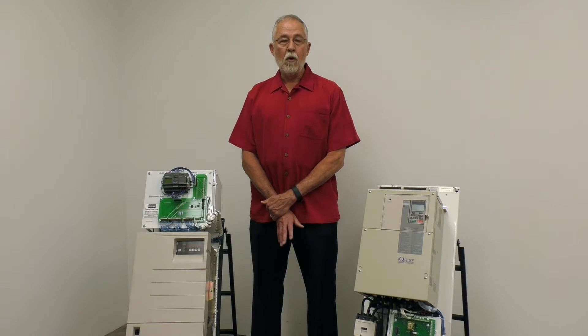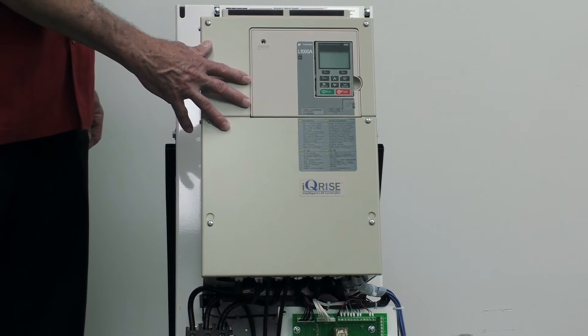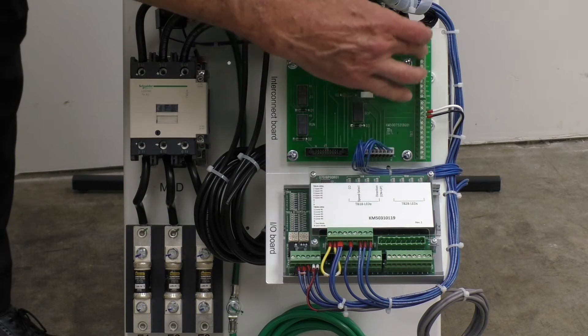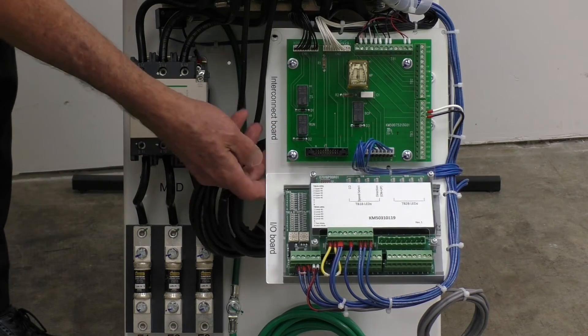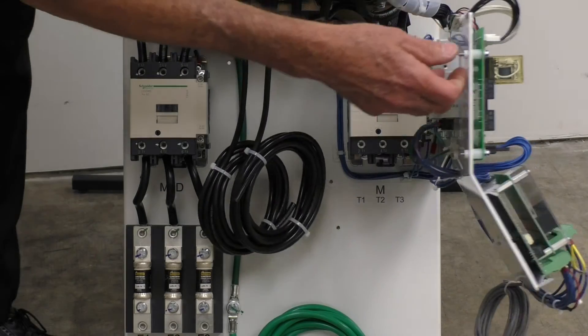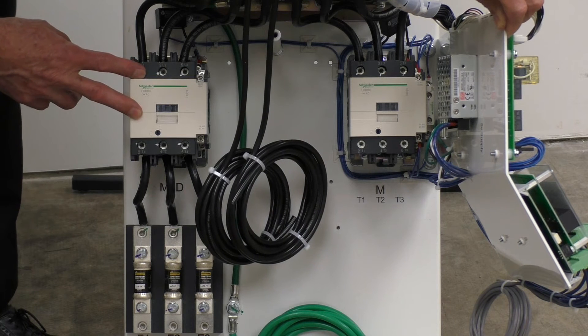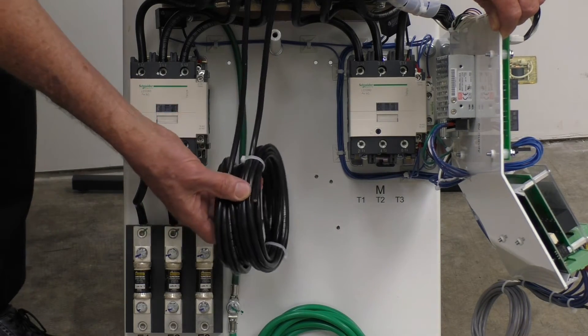These drive panels include all the instructions necessary, the parameter list, all the hardware necessary, and also the new wiring diagrams. The AC drive panel utilizes the Yaskawa L1000A drive. It has an interconnect board where all the small field wires can be landed, making it easy because everything else is pre-wired. The main wires are connected to the incoming line right here, and your motor leads are connected to the brand new M-Contactor.